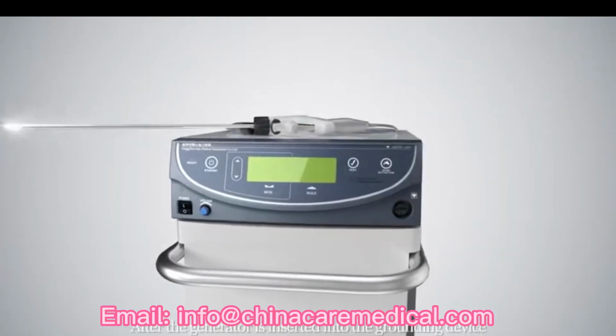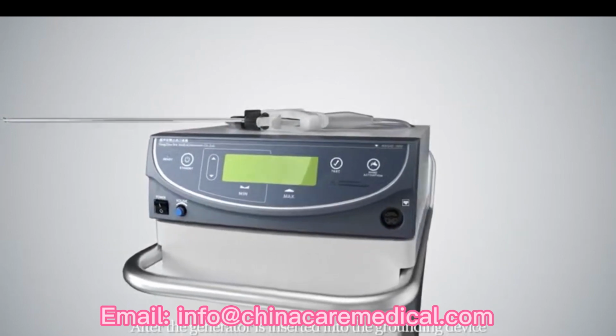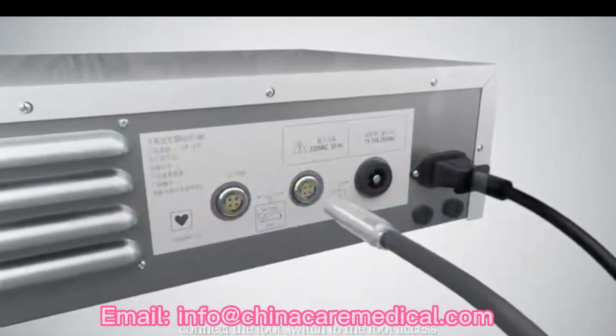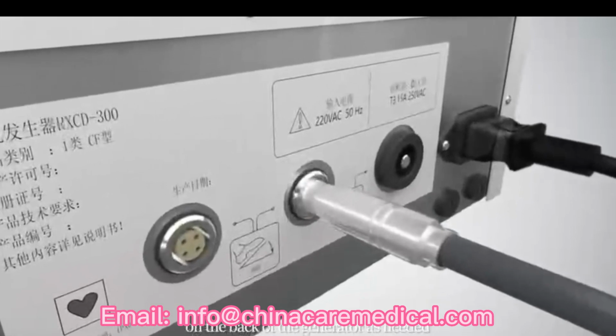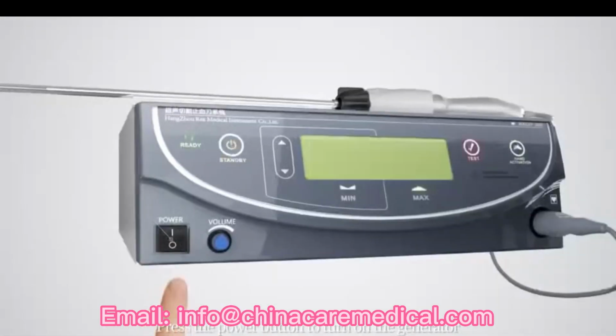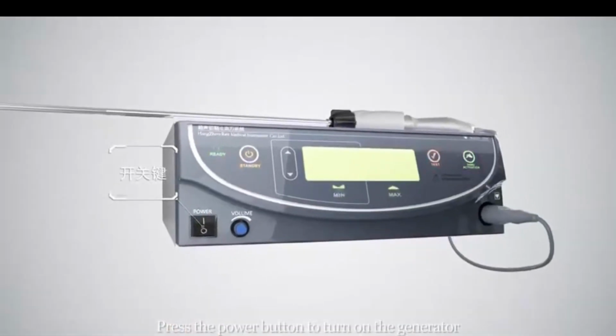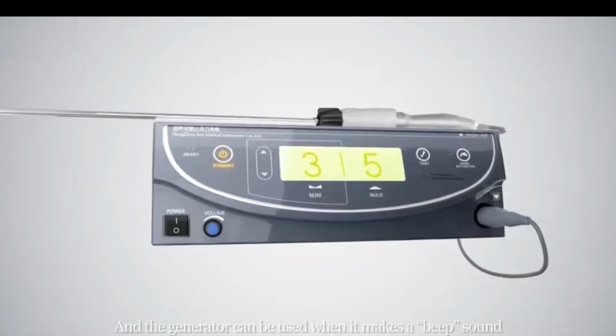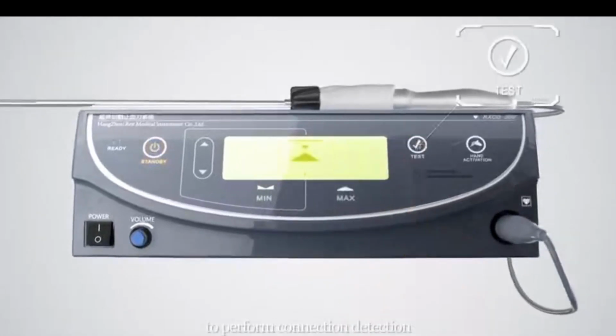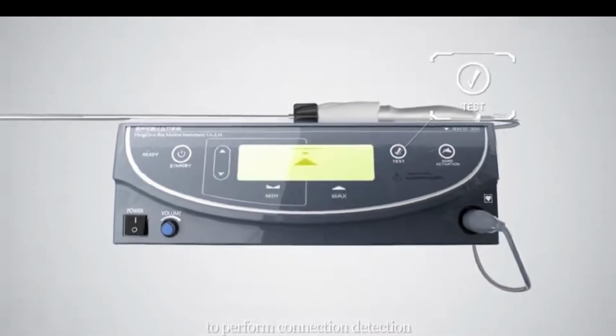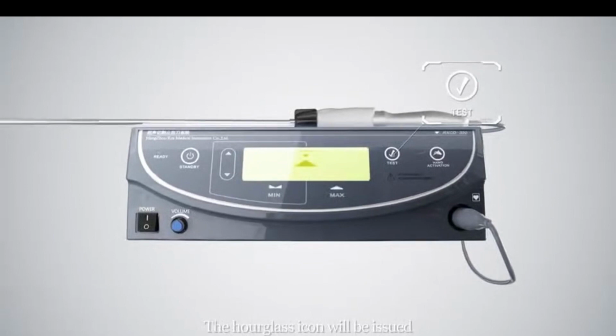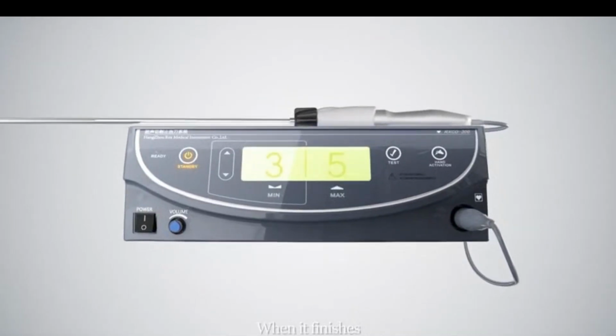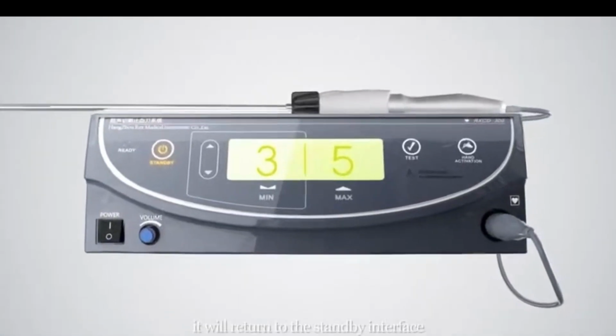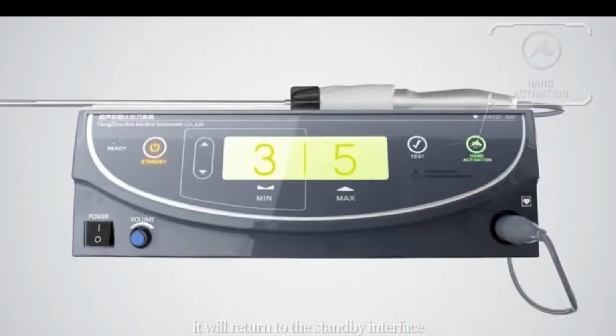After the generator is inserted into the grounding device, connect the foot switch to the foot access on the back of the generator as needed. Press the power button to turn on the generator, and the generator can be used when it makes a beep sound. Press the test button to perform connection detection. The hourglass icon will be issued and beep will be issued when the detection is completed. When it finishes, it will return to the standby interface.